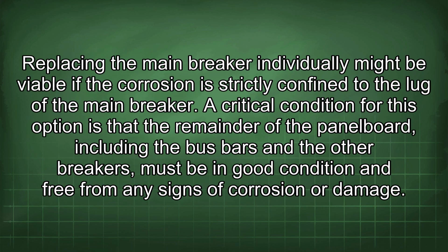swap. Replacing the main breaker individually might be viable if the corrosion is strictly confined to the lug of the main breaker. A critical condition for this option is that the remainder of the panel board, including the bus bars and the other breakers, must be in good condition and free from any signs of corrosion or damage.